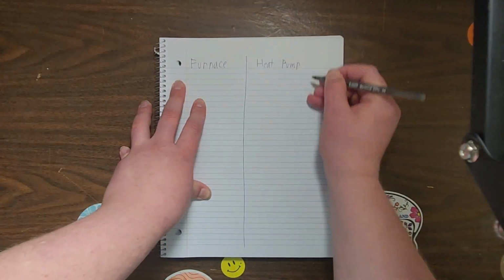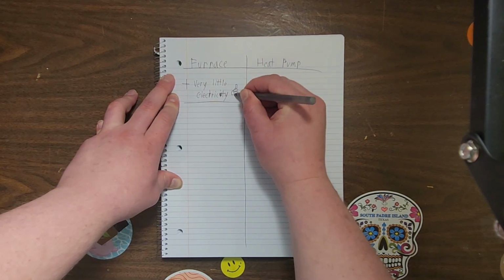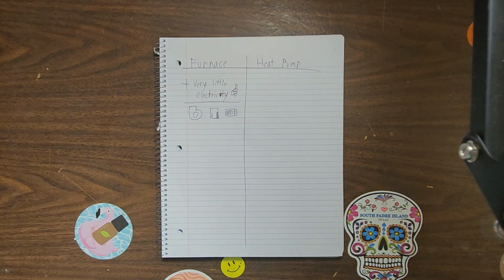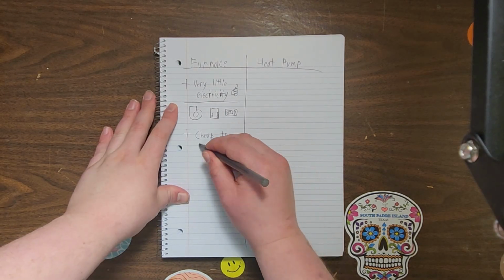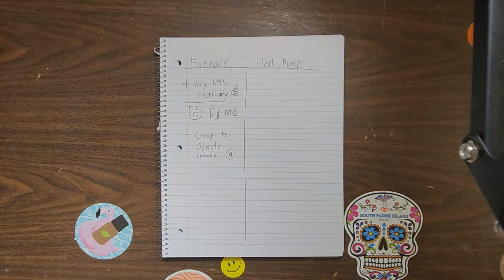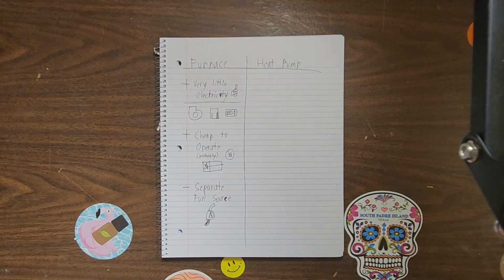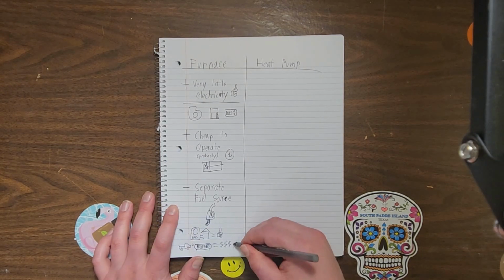First of all, the pros of a furnace. First, furnaces use very little power. In a furnace, the only devices using any power are the blower motor, furnace board, and thermostat, unless you have any sort of indoor air quality devices connected. Second, furnaces have the potential to be very cheap to operate. This will very much depend on the fuel that you're using and how much that fuel costs. But in areas with cheaper natural gas and propane, like Texas for example, furnaces are a great option for heating. However, the main drawback of furnaces is that they require a separate fuel source. This isn't an issue for many homes, as most of them have natural gas plumbed into them. But if you don't, you're dependent on getting fuel from elsewhere, like propane.